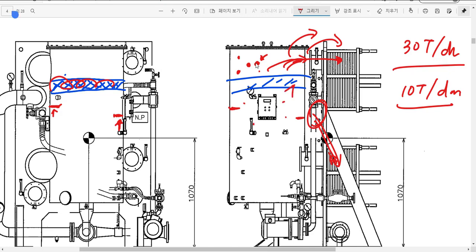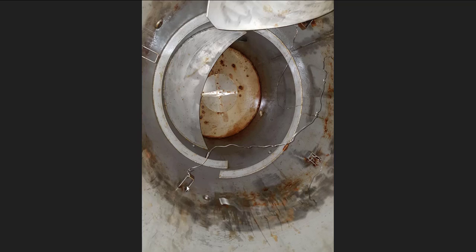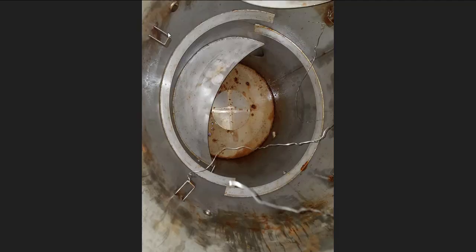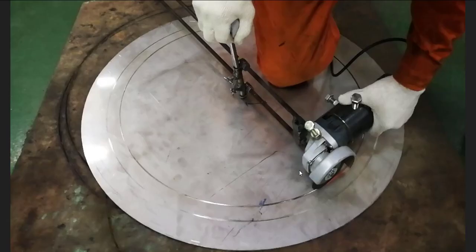The valve opens to bypass all the time because the water mist is not screened out by the demister. This is my solution: the original screen plate and the original demister located position. Let me show you - they have a large plate down below with a large size screen and small plate like that, but this is not perfect.